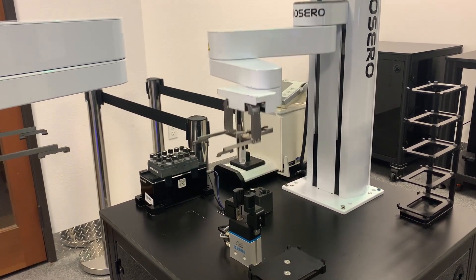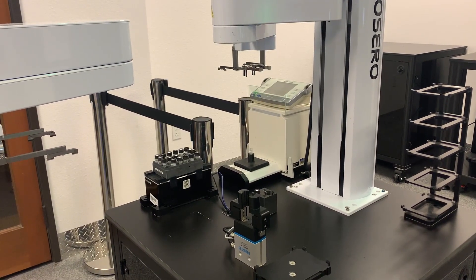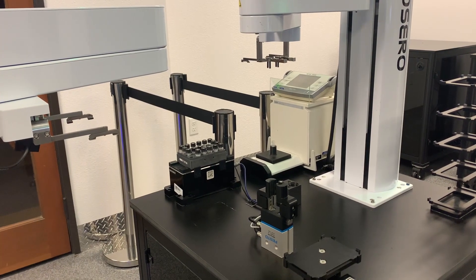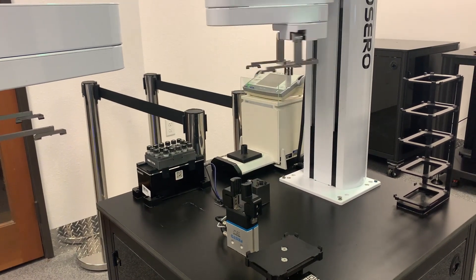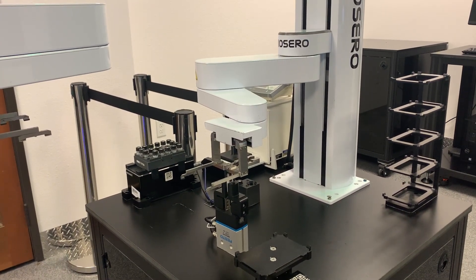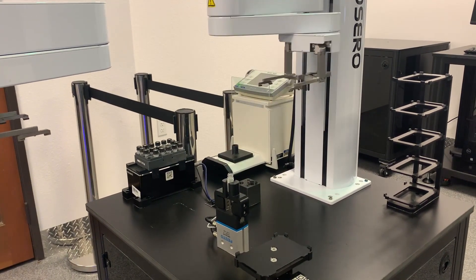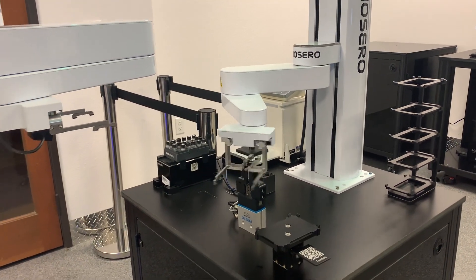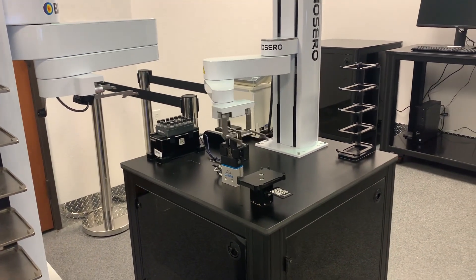The robot arm is collaborative and is commonly used in lab automation. The machine vision system is based on a high-performance camera and provides the ability to get and put labware with a very high degree of accuracy. All autonomous ground vehicles have a limited positional accuracy — Yoda's positional tolerance at best is plus or minus 20 millimeters. By adding a machine vision system, we can close the gap. Once Yoda arrives at a destination, the vision system identifies the exact location of the nest and makes an appropriate adjustment to the arm's teach point.